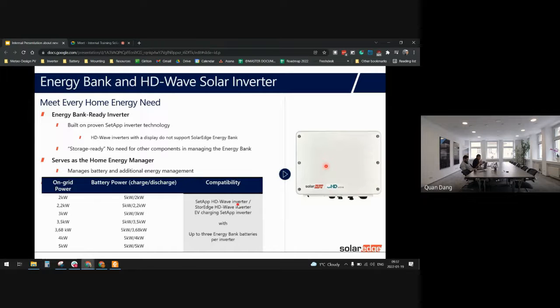So what is the first message? This battery only works with the HD Wave SetApp, HD Wave inverter. That means only single phase inverters can work with this battery, not 3-phase. That's the first thing. Second thing is about the charge and discharge rate - they say maximum 5 kilowatt charge and discharge from the battery. However, the charging will always be 5 kilowatt, but the discharge rate always depends on the size of the inverter. So if the inverter is 2 kilowatt, they can discharge maximum 2 kilowatt.